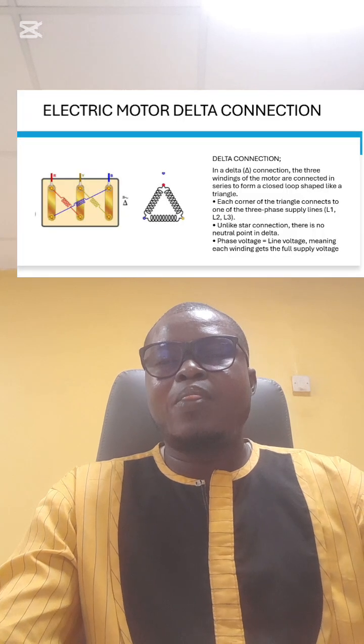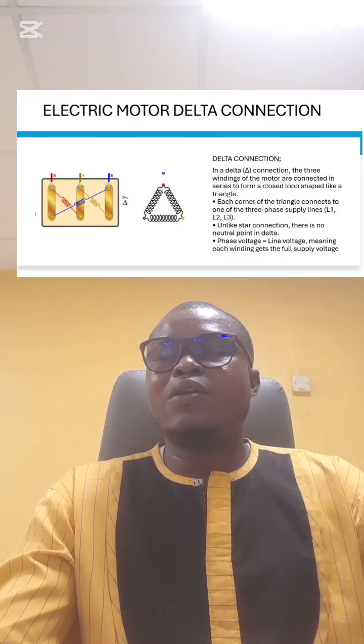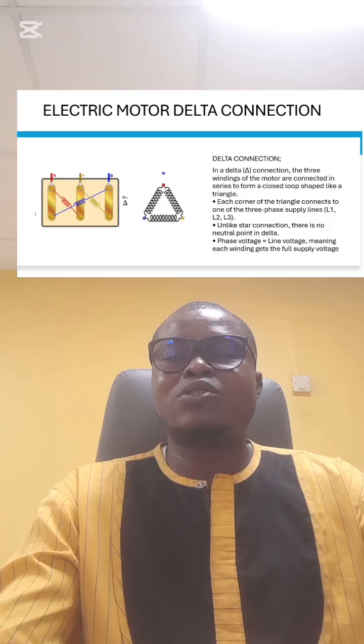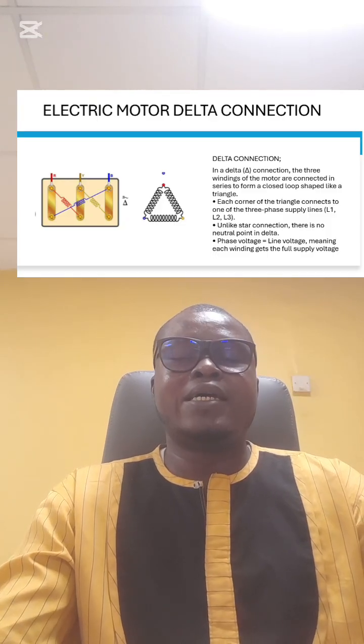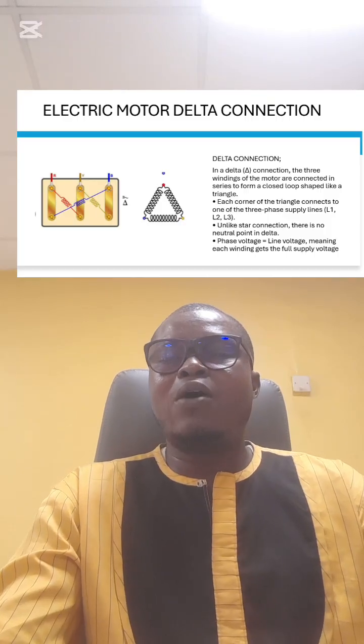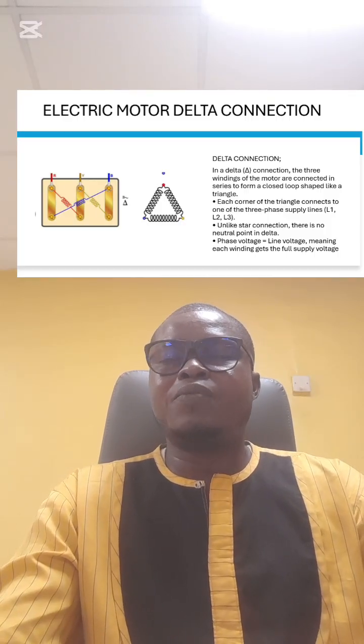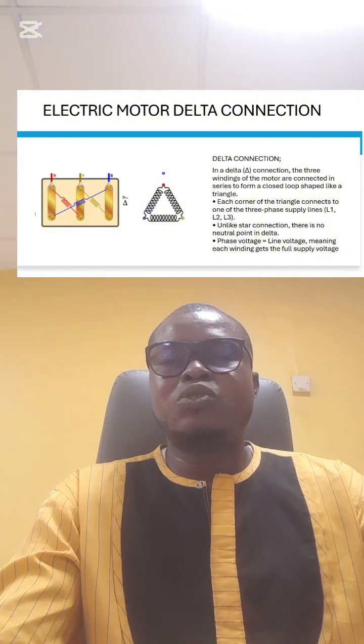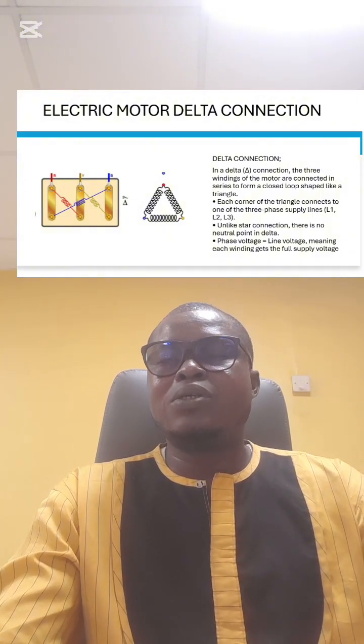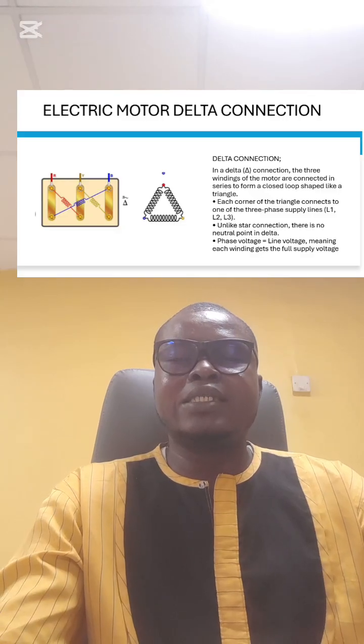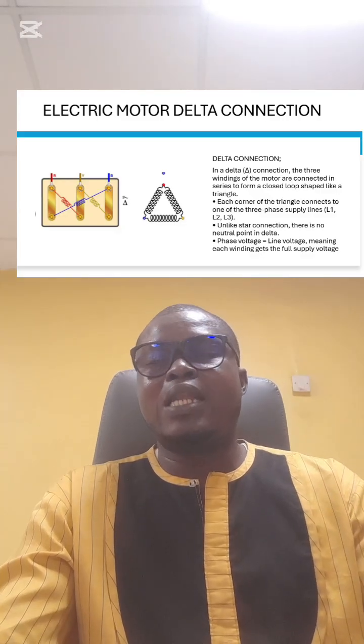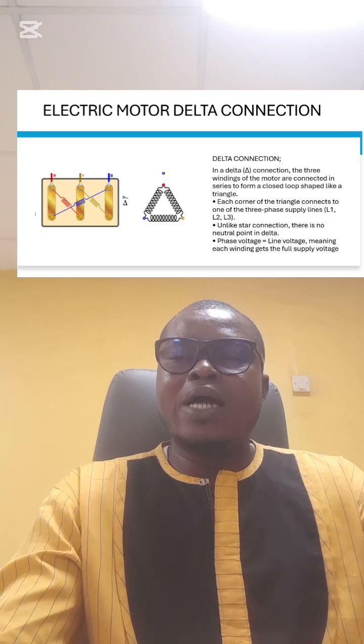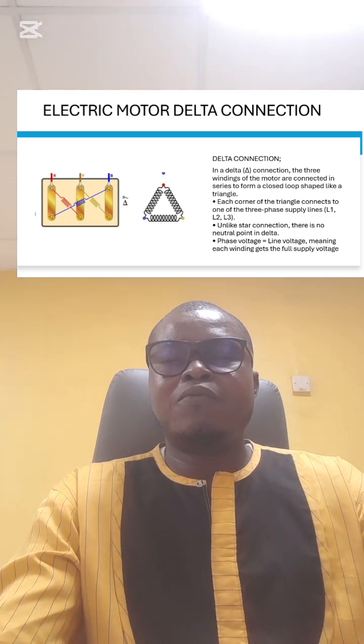We cannot start talking about a star connection without discussing the delta connection. In a delta connection, the three windings of a motor are connected in series to form a closed loop shaped like a triangle. Each corner of this triangle connects to one of the three-phase supply lines, L1, L2, and L3. Unlike the star connection, there is no neutral point in a delta connection. Phase voltage equals line voltage, meaning the winding receives full supply voltage.